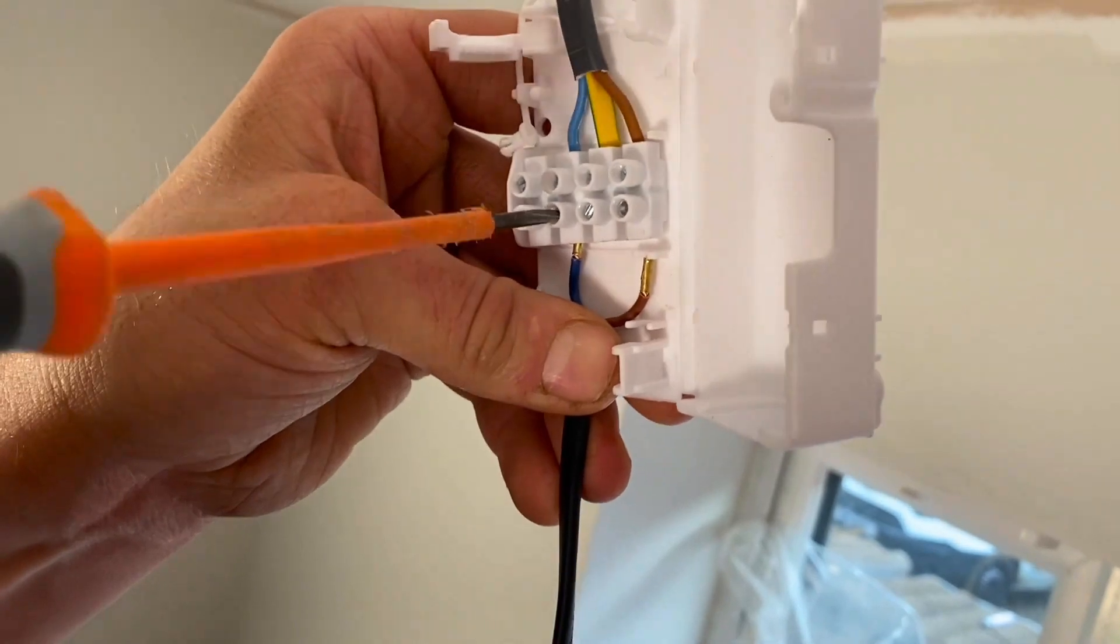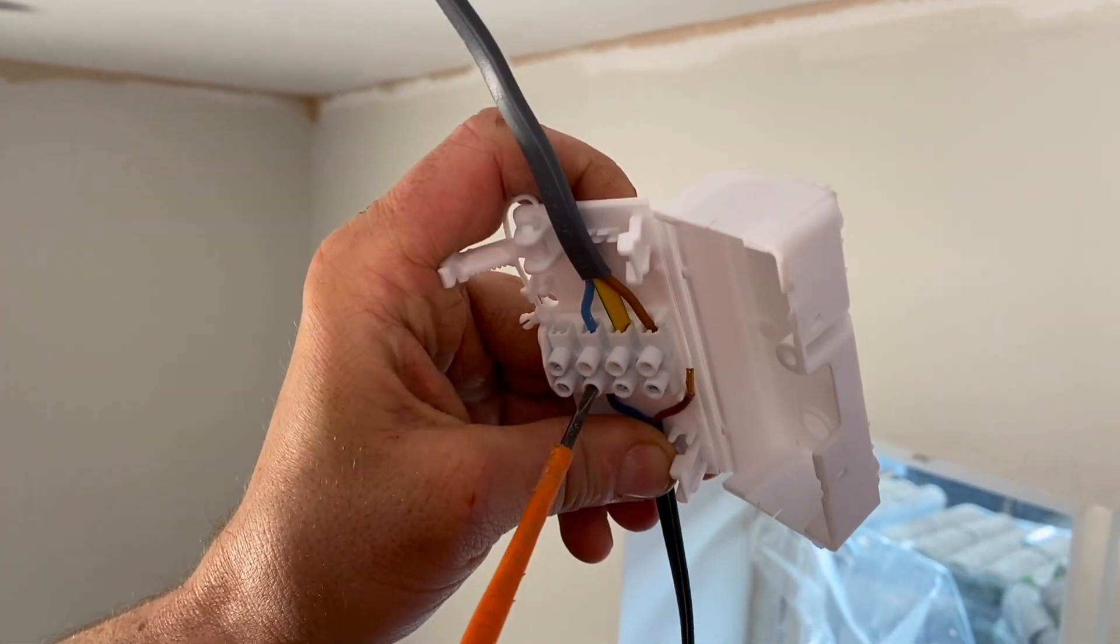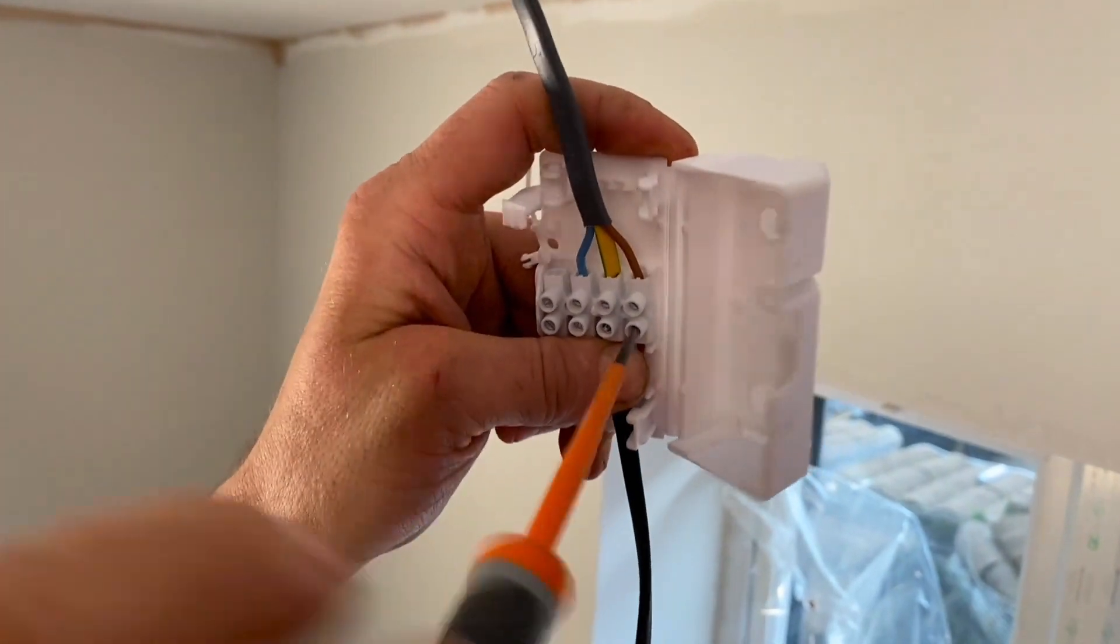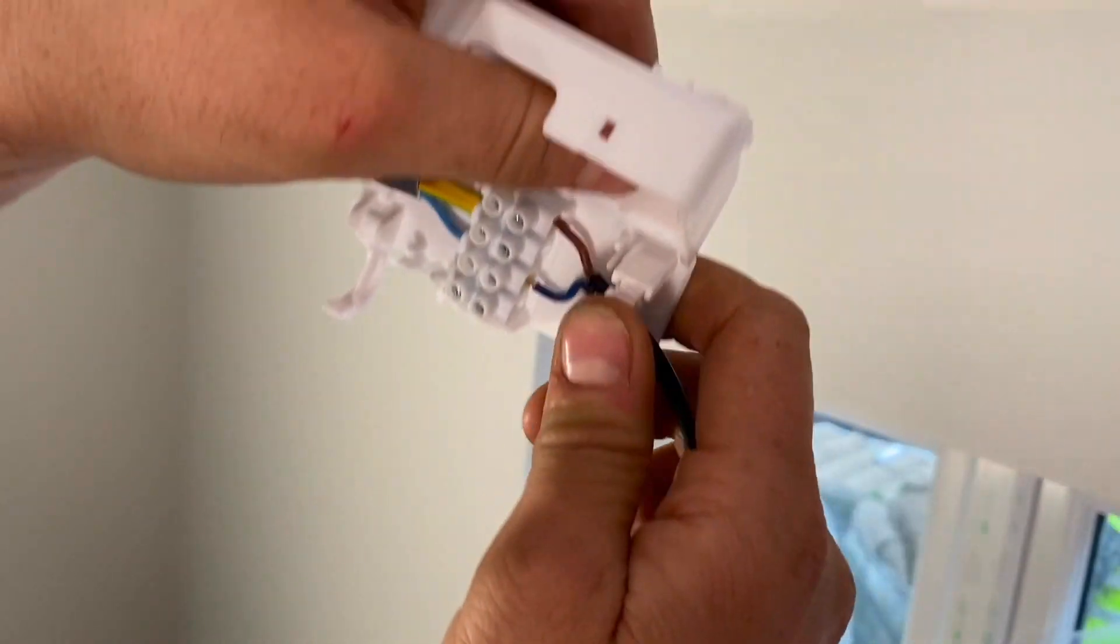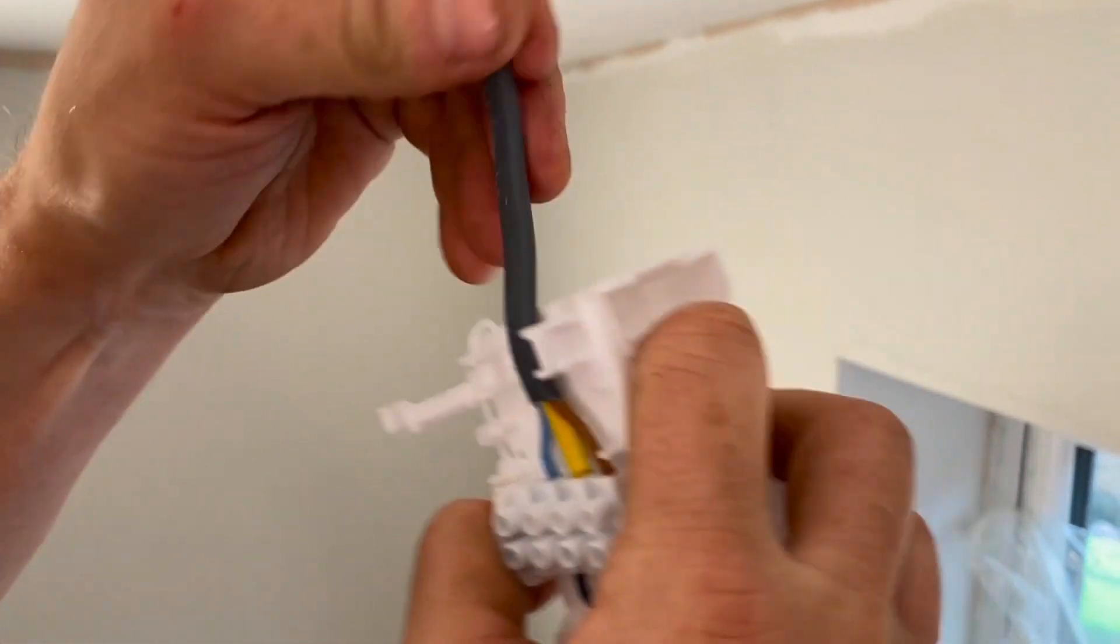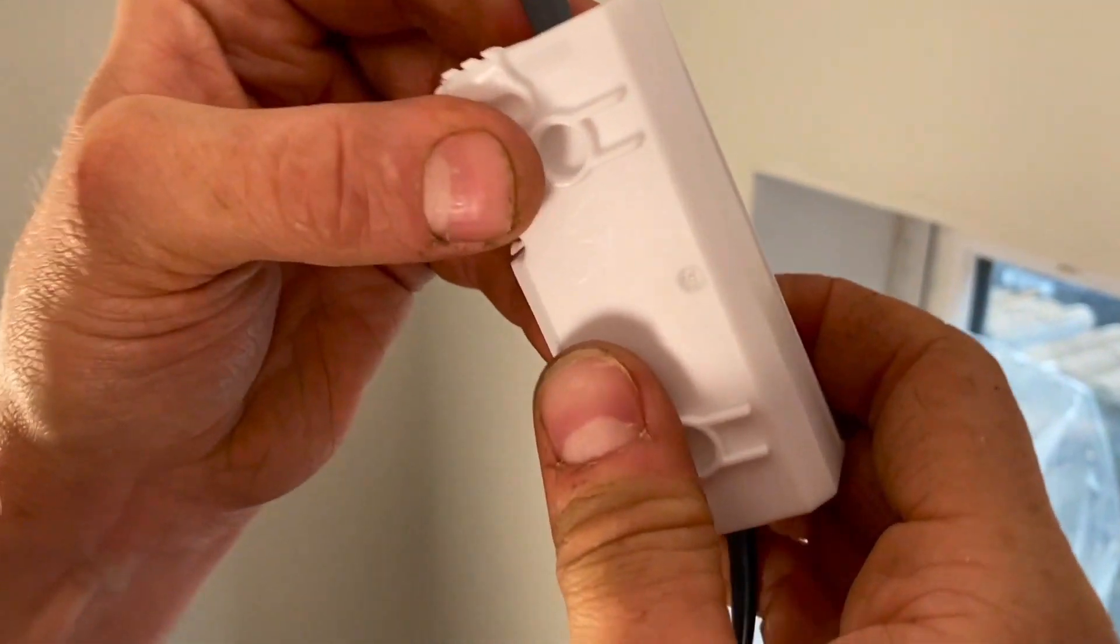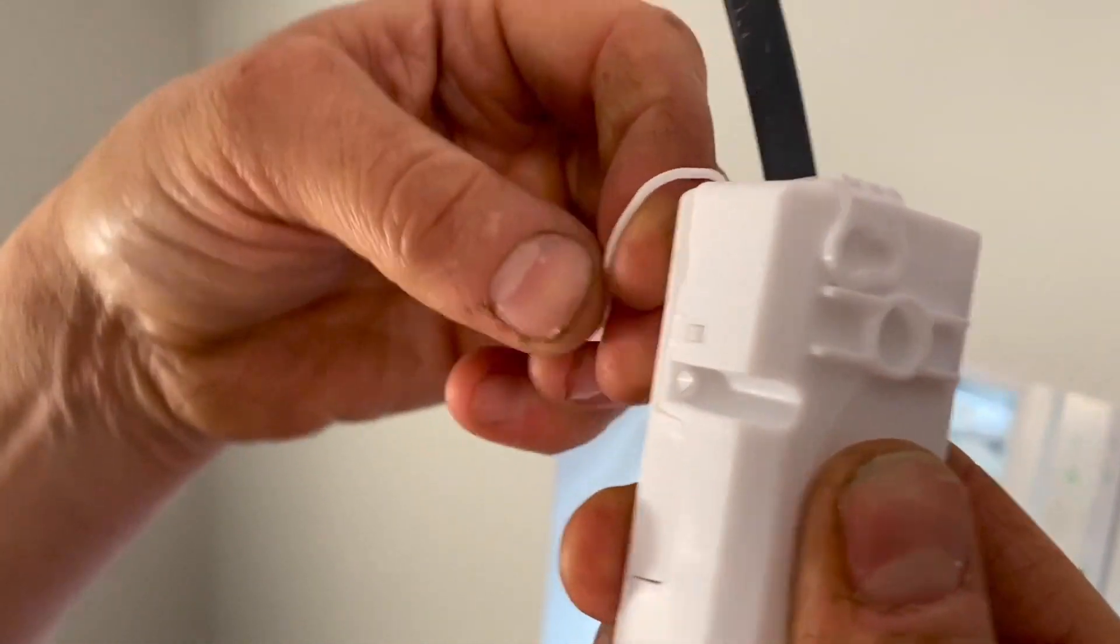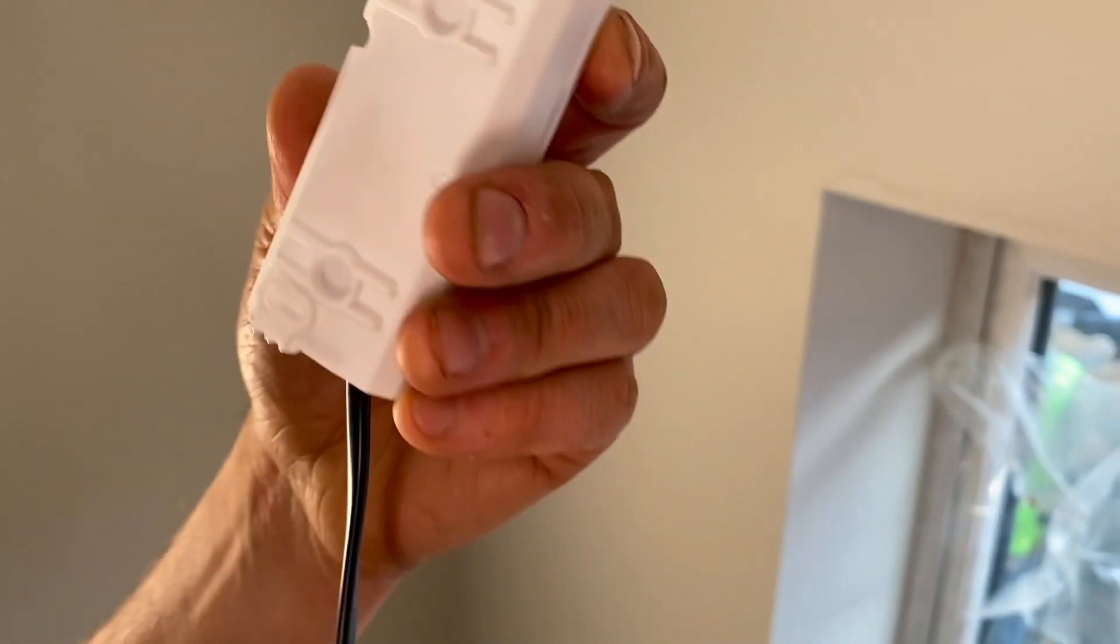Sometimes you get those really small spotlights that have the tiny cut-out holes. Electricians of a certain age will remember the old round brown junction boxes and you had to sort of cut a slot into the ceiling to get them through a tiny hole. Well, we've not got that problem here, which is really good. Just finish those terminations off. And again, we've got all the same features that we had before. Use of tools is minimized. We've also got the cord grips, which will clamp down onto various sizes of conductor and cable as well, and even accommodate round flexes. We noticed in the cable entries earlier, you've got a little slit in the entry part, which just adapts itself around the cables that you're installing. Pop the little retaining pin in to keep that lid securely closed. Nice, neat little connection, that.